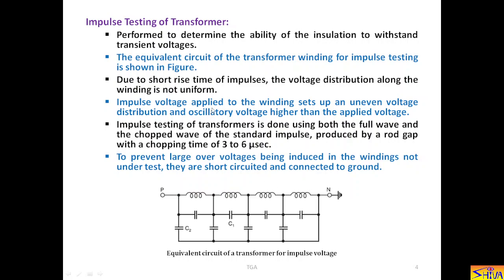Impulse voltage applied to the winding sets up an uneven voltage distribution and oscillatory voltage higher than the applied voltage. Because here it is capacitive network. So, due to the presence of this capacitance voltage increases along the winding. It becomes more than the applied voltage.